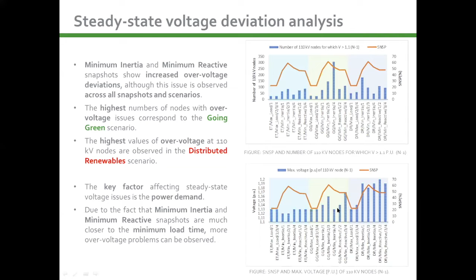Again, the key factor affecting steady-state voltage issues is the power demand. Due to the fact that minimum inertia and minimum reactive snapshots are much closer to the minimum load operation conditions, more over voltage problems can be observed for these operational scenarios.